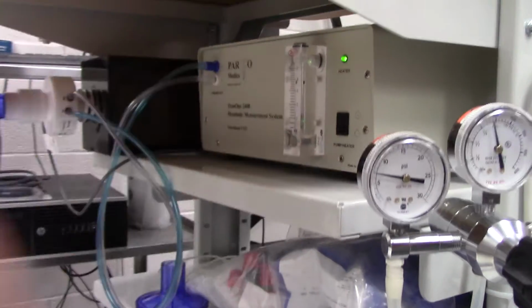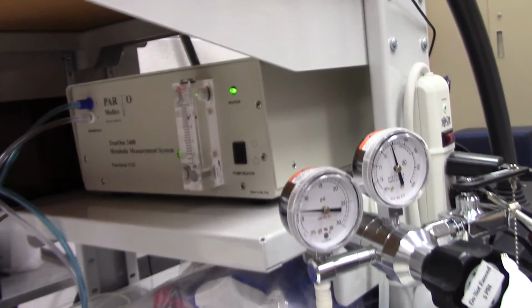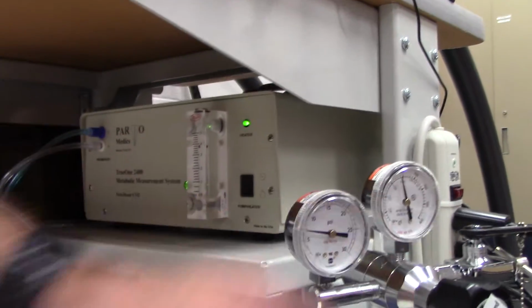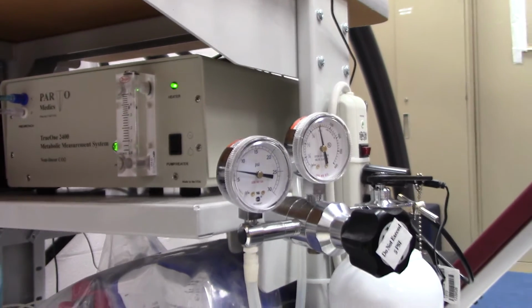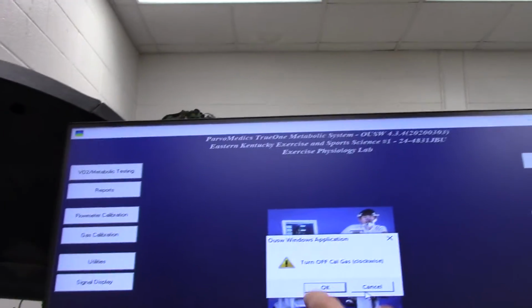So now we're drawing, we should see that value. If this goes to 0, that means we don't have enough pressure going through, and it's done. If it goes too high, this would blow a sensor, please, God, don't let it happen. So never, ever touch this dial if you can. Okay, so now you can see how the air O2 is way low.